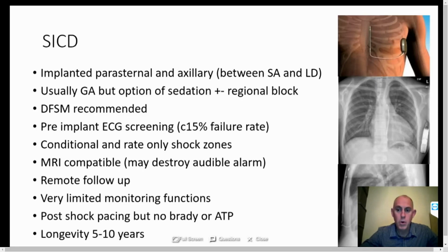Defibrillation safety margin testing is strongly recommended, and the labelling on the device requires you to perform this when you implant it, in contrast to transvenous devices. Patients need to pass pre-implant ECG screening, with approximately a 15% failure rate.